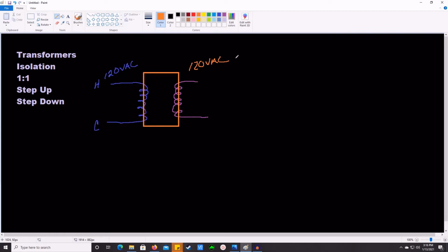Now, the last thing is, when you're looking for an isolation transformer, you're going to see this a lot: VA. Why isn't it just in watts? Well, because it's the load that they're going to put across it, and it can be different types of loads — resistive, capacitive, inductive. There's a lot of different factors which will change the math on what the actual wattage output is.